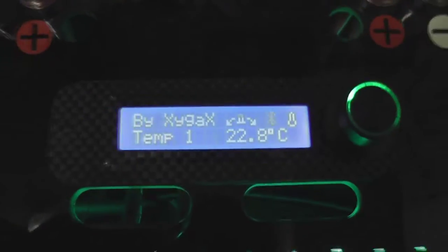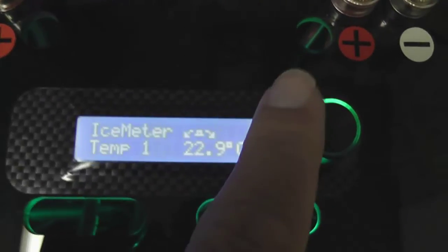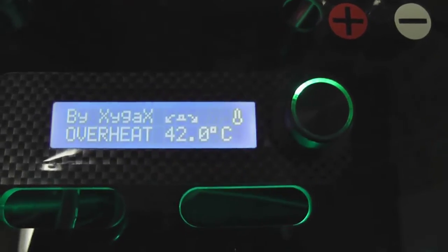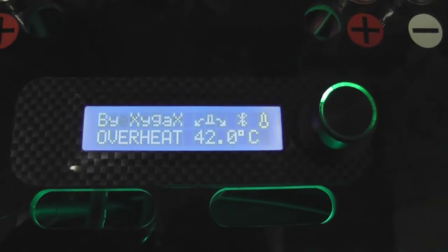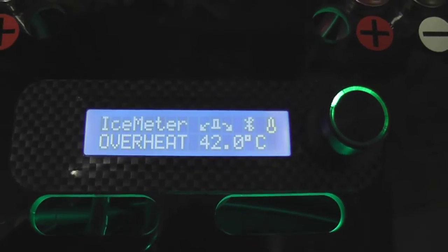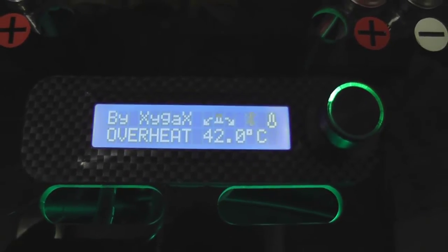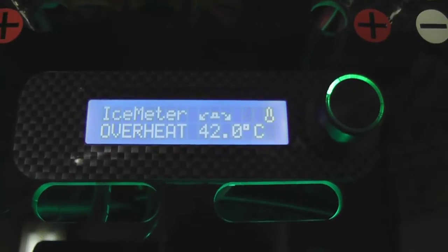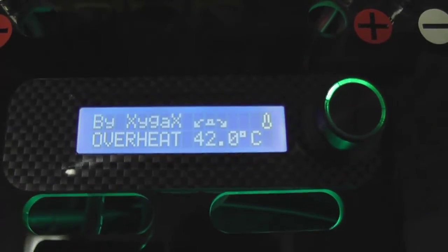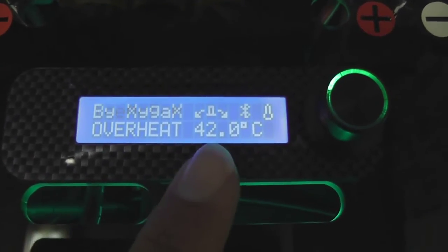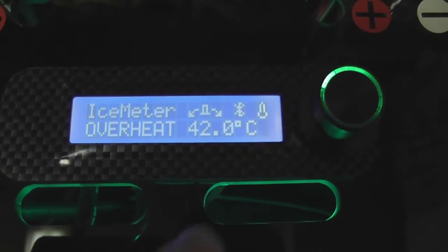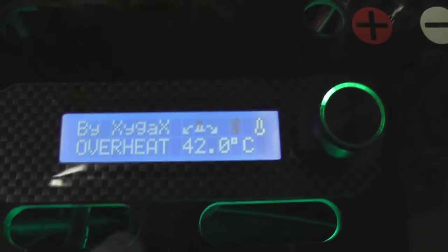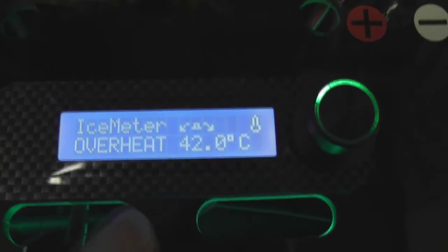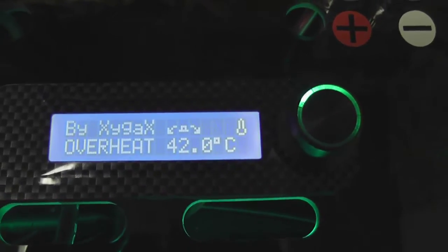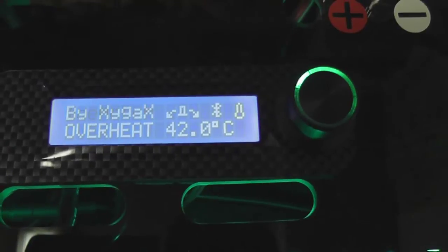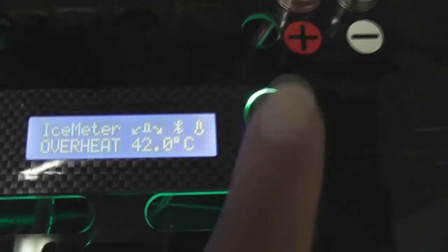Okay, so we'll scroll the wheel again. Overheat. We've got an option in this unit now to specify an overheat temperature, at which point both power supplies would then be shut down, and this would be based on that temperature sensor. So I've got it set on this case to 42 degrees C, so if the temperature within the case rose to 42 degrees C, or just above actually, again both power supplies would be shut down, the charge cycle would be stopped, and everything would just sit there.